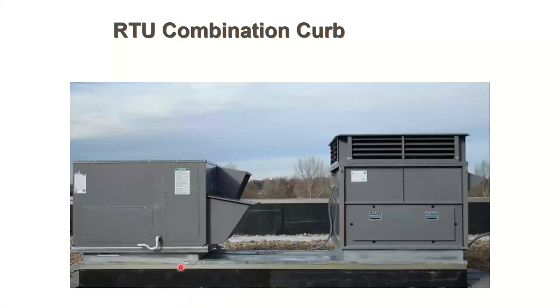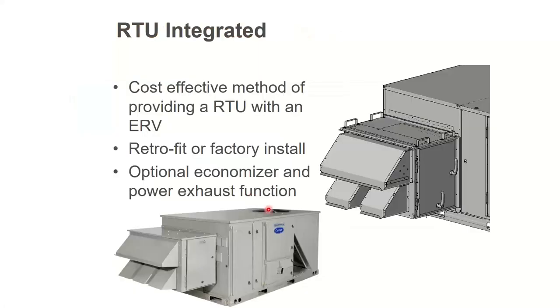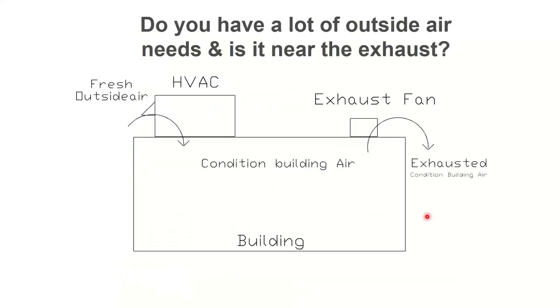The return comes up and doesn't go into the unit. It goes down the other side of the curb and goes out as the exhaust. My ERV exchange is over here. The nice thing about this is I still have the economizer available for an economizer day. I can shut the ERV off and economize when I want to do free cooling. And there are also little small ones you can bolt onto the side of a packaged rooftop unit. There are lots of different ways to get that done.